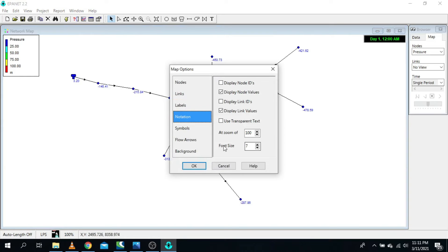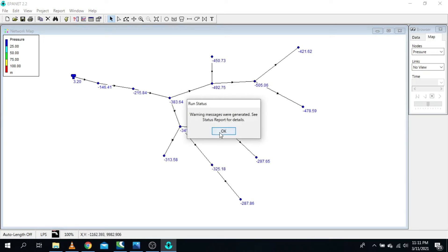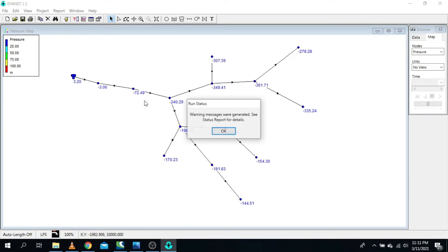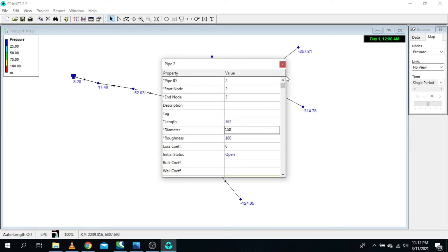First, increase the font size so we can see values more clearly: go to Options, then Notation, and increase font size to 8. The gravity main is supposed to carry water to all nodes, and pipe 75 mm is too small. We see a pressure of negative 146.41. Let's increase the gravity main pipe to 110 mm — pressure improves. Increase further to 150 mm — now we have positive values.